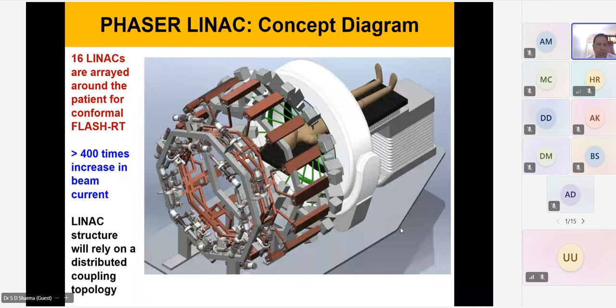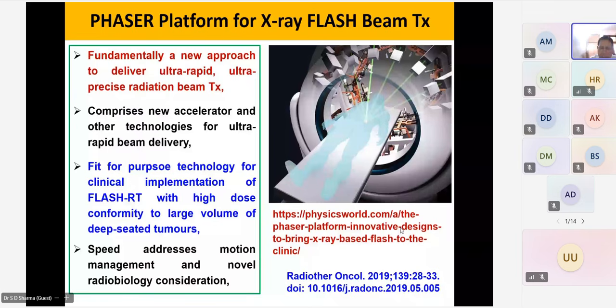You can see multiple accelerators, 16 LINACs, arrayed around a ring gantry, and the beam current is almost 400 times that of our available accelerator. So this helps in delivering treatment from multiple directions at the same time, which results in the delivery of the dose at a higher dose rate. This way we achieve flash radiotherapy treatment with the PHASER platform.